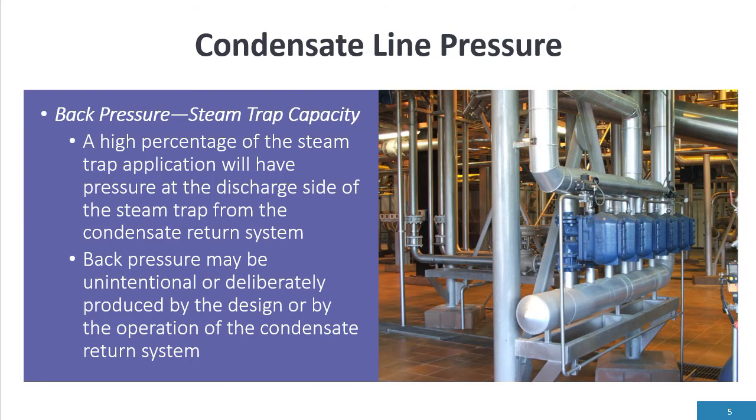Now back pressure in the steam system. The back pressure is always going to be there in the steam system. The back pressure can be intentionally designed or because of the installation. A high percentage of steam trap applications are going to have pressure on the discharge side of the steam trap. One of the biggest problems we have in steam trap sizing is we don't know the back pressure against the steam trap.